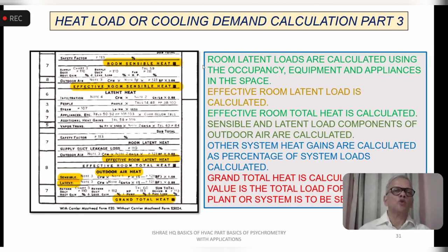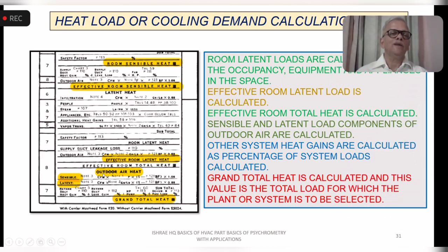Then you have this room sensible heat you have seen before. This is the room latent heat. Room latent loads are calculated: occupancy, equipment, and appliances. Effective room latent heat also is calculated. And then you have the outdoor heat because you know the outdoor air quantity. You know the ventilation rates as we have seen in the previous slide. So you know the outdoor air heat, the room latent heat, and the effective room latent heat.